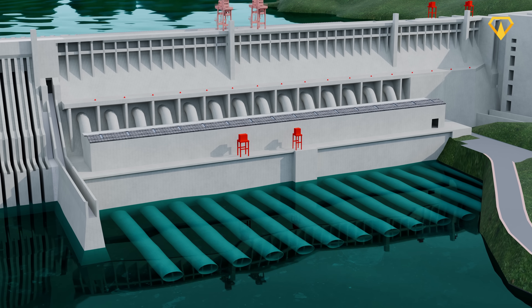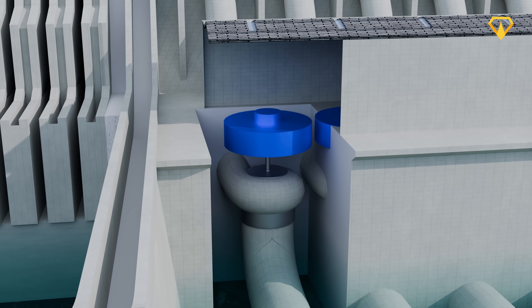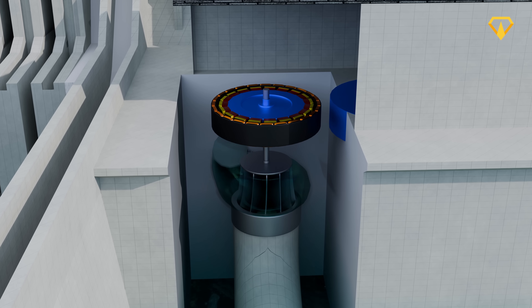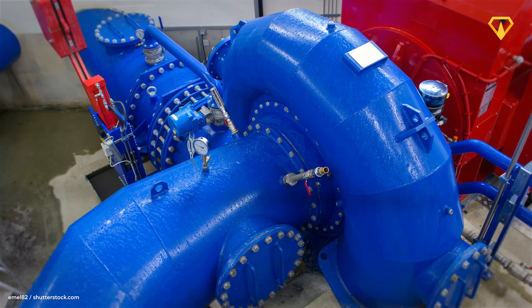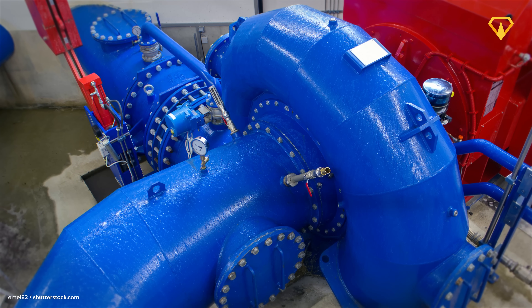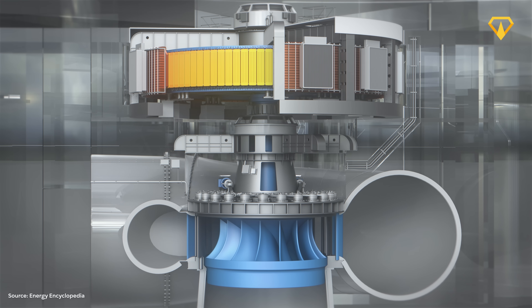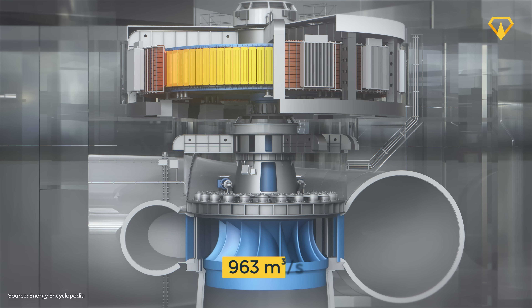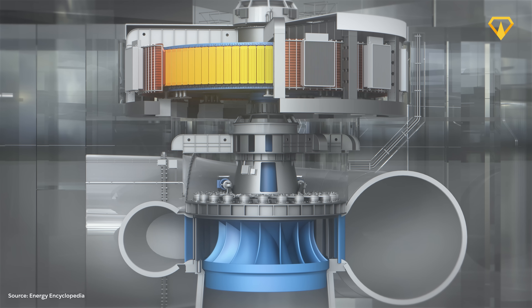It all starts with the massive Francis turbines, located inside the concrete powerhouse buildings near and under the main dam structure. There are 32 of them, and each can crank out 700 megawatts of electric power. These turbines are absolute monsters, unlike any other turbines ever created before — engineered to handle a water flow of up to 963 cubic meters per second and a crushing height drop of 113 meters, while enduring extreme pressures that would obliterate conventional turbines.